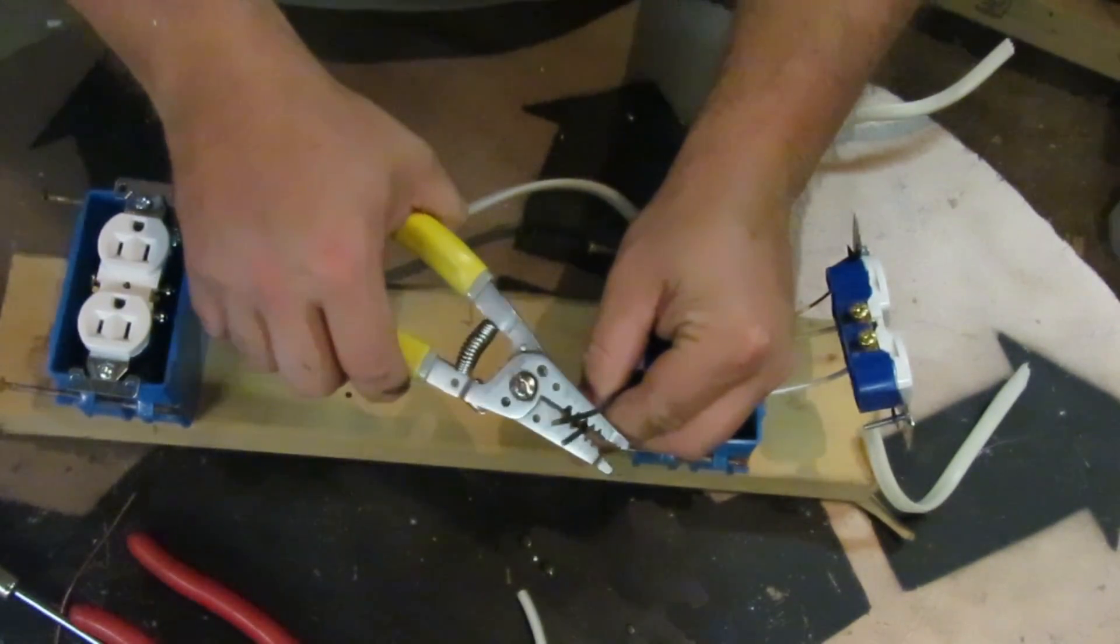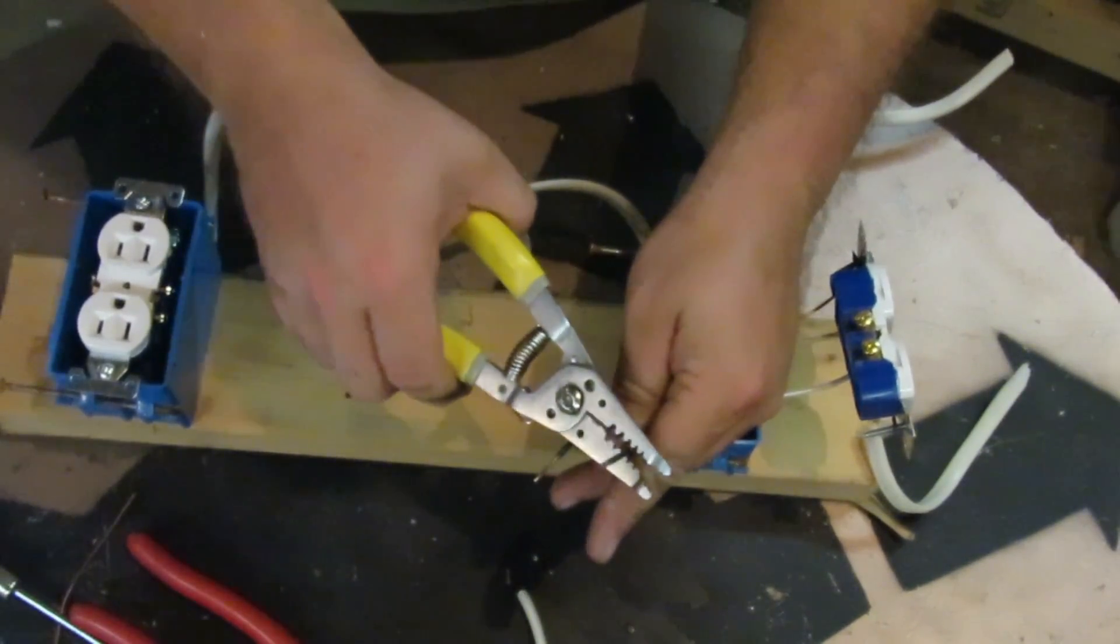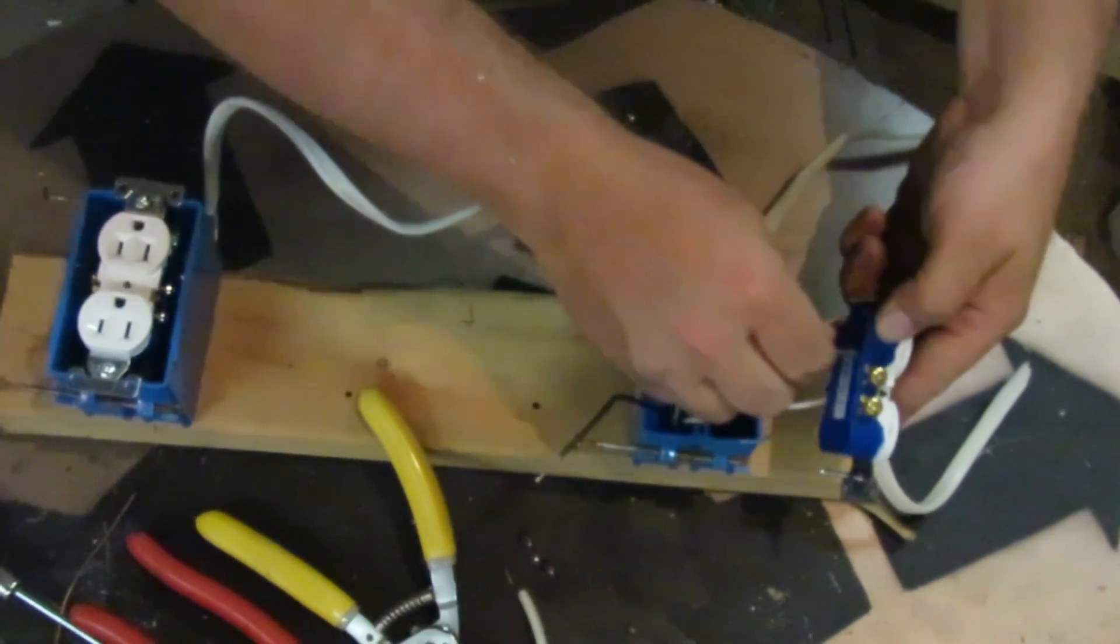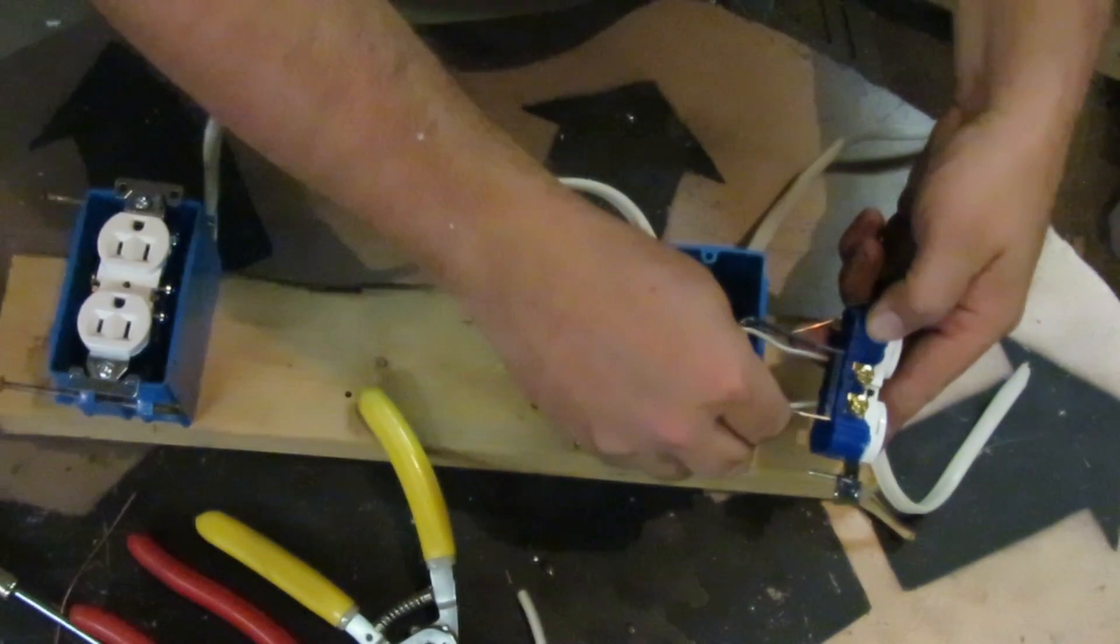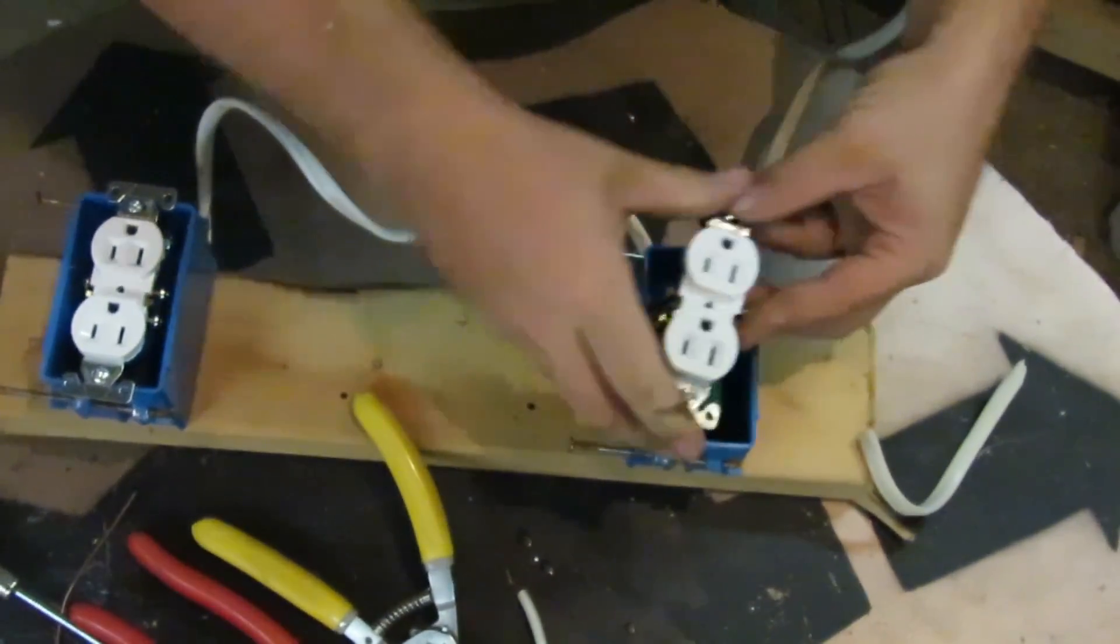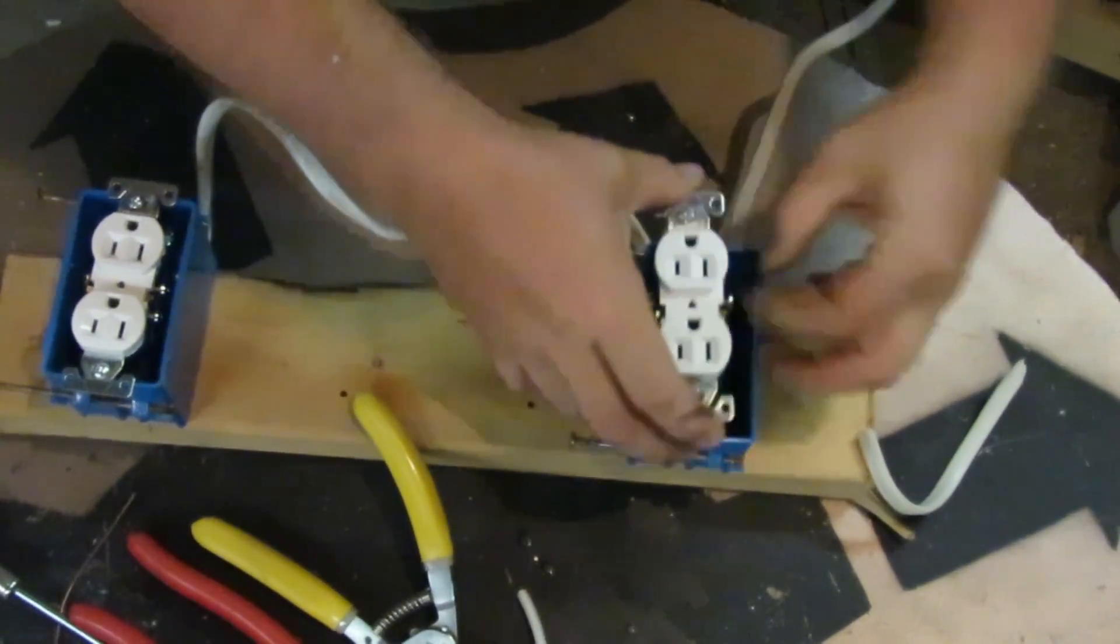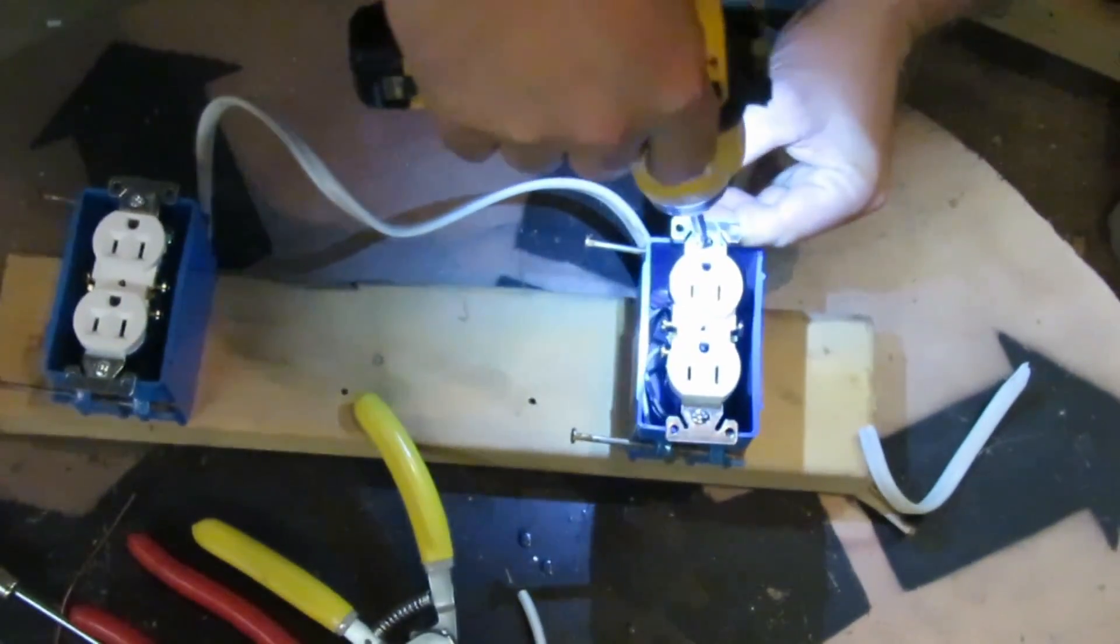And then strip off your black wires. And your black wires always go under the brass colored screws. And here I'm just pushing them both in the back. I'm stuffing the receptacle into the box, screwing the receptacle into the box, and then I'm done. And that's all there is to it.